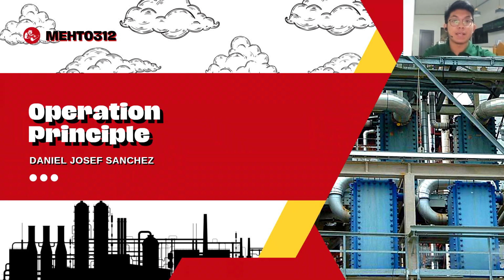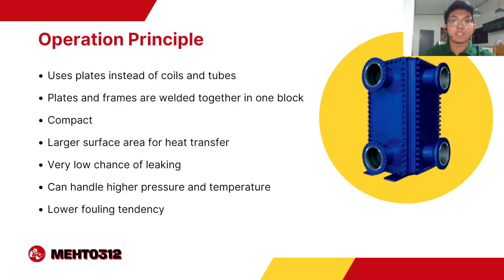I will now discuss the operating principle behind the welded plate heat exchanger, how it works and functions, and its main differences from the other heat exchangers. So first, its main differences from other heat exchangers. Its most observable difference is that it uses a series of plates instead of coils and tubes.